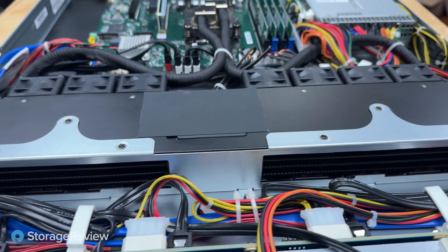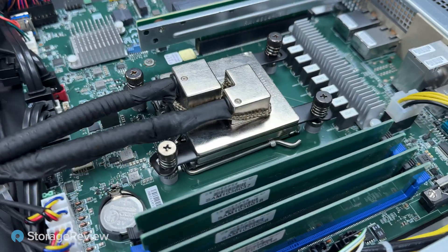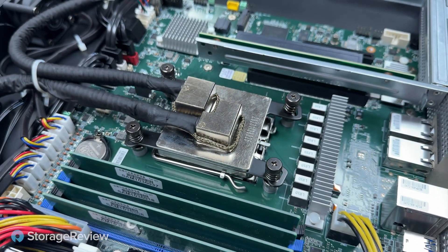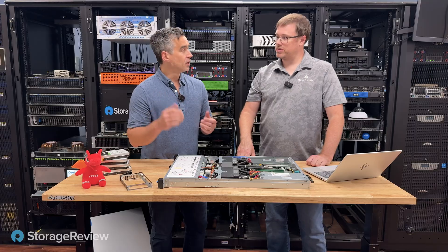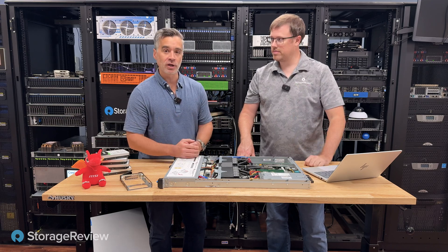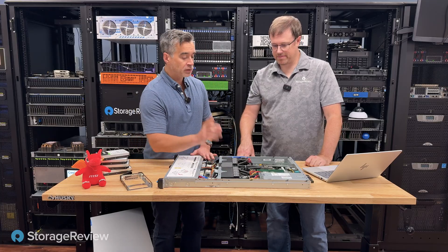There are seven fans and just a basic in-and-out on this loop. These are normally rated at around a five-year window. Around five years, they're expecting you to swap them out — it's not really a fluid swap, it's just that you start getting buildup in the heat sink itself. Inside the cold plate, there are little ridges — turbulators — and any buildup reduces the flow, like an artery that eventually needs a stent. Since you can't put a stent in the system, you replace it every so often.